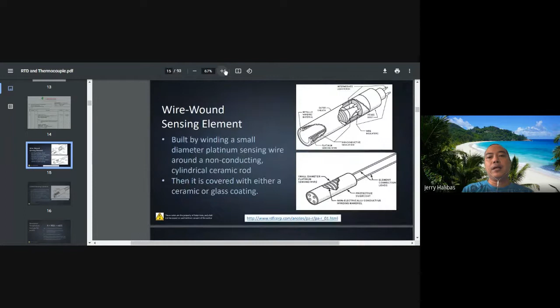Okay, as well as the coiled sensing type or sensing element. Okay, so we go now to the formula, no? So the linear formula of the temperature, the resistance of the RTD. So where R is the final resistance, the R0 is the initial resistance of the RTD, multiplied by 1 plus alpha. Alpha is the temperature coefficient, no? Then the delta T is T final minus T initial.